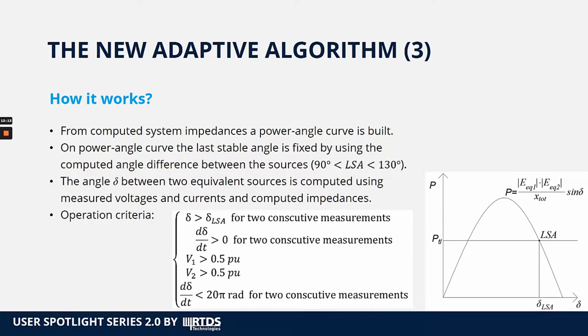The voltage magnitudes here need to be larger than 0.5 per unit, and this is set to check if the bus bars and the transmission line where the protection is implemented are actually energized. The derivative value of the angle needs to be smaller than 20 pi radians for 2 consecutive measurements, and this acts as a fault detection unit for the protection algorithm. When there is a fault in the network, there is a very high increase in the computed angle difference, but during a fault in the network, this protection should not operate. Therefore, this is used to block the protection operation during fault events.